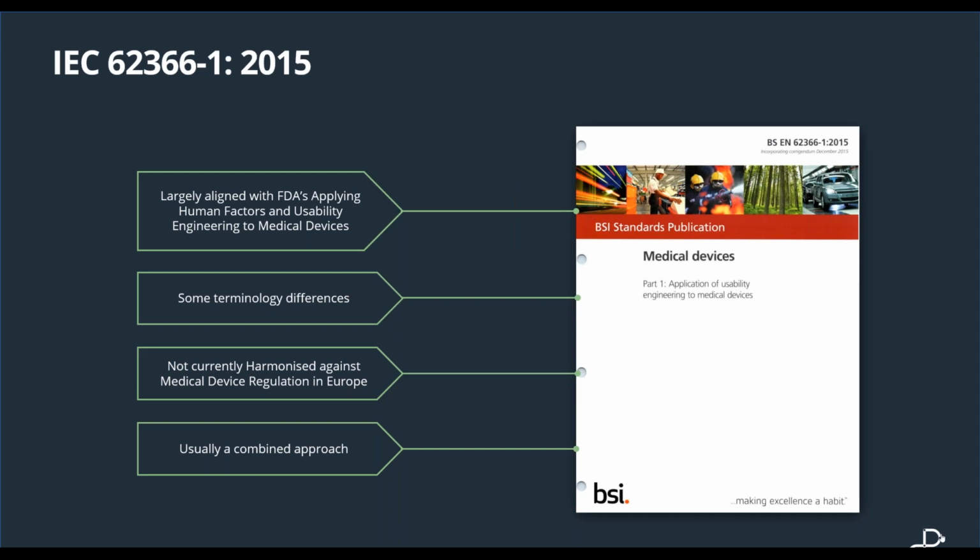It's worth pointing out, with the advent of the medical device regulation in Europe, this is another one of those standards that is not currently harmonized. So as with anything state of the art, if you're looking to implement 62366 Part 1, which we strongly advise that you do, it's worth having another check against the medical device regulation to see what the additional requirements are, to make sure there aren't any gaps.